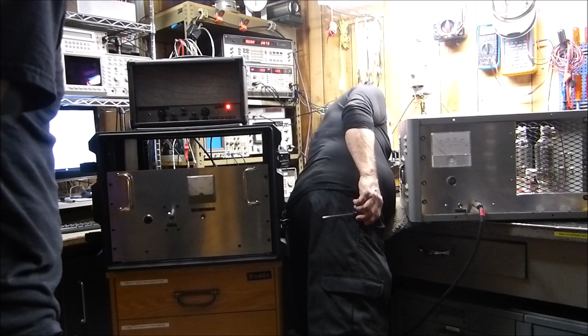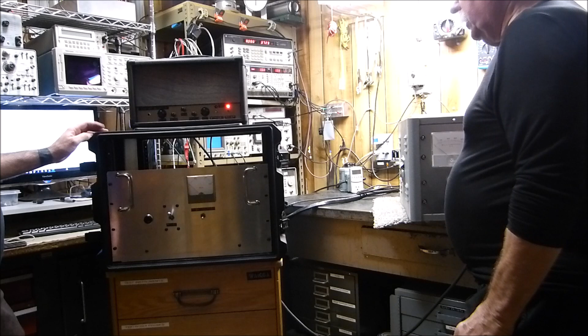And because this should, the filament should come on and the bias should come up. We also don't have, there's no, the fuse indicator's not on. It shouldn't be, because if it's on, the fuse would be blown. Oh, it's the other way around. Gotcha. Yeah, okay, well we got something silly.